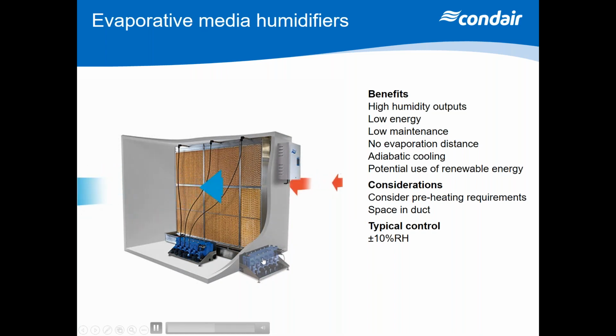We also have a UV light installed in the tank there, so we get a high kill rate of any bacteria. And when we don't have any use of, no demand, the whole unit will just dry down, so we don't have any bacterial growth. We do, though, have to consider preheating the air, of course, because it's an adiabatic process. My limiting factor is controllability, because I'm either turning on or off certain sections of this humidifier. So I'm either running one or a number of these pumps. So typically it will give me plus or minus 10% RH control.